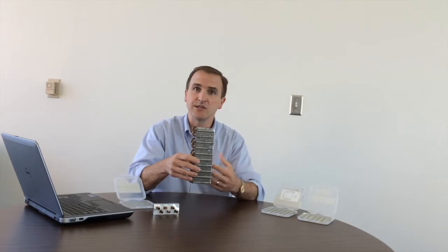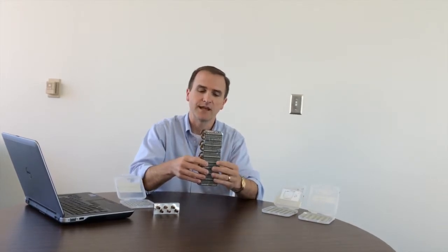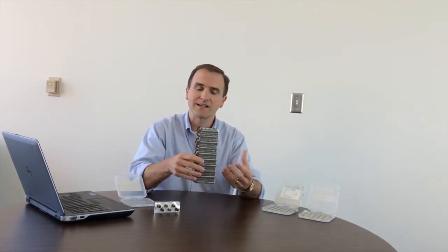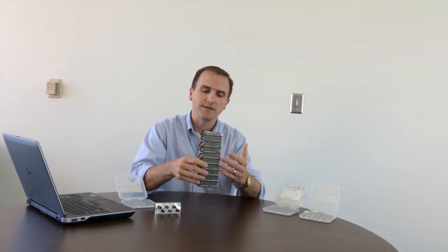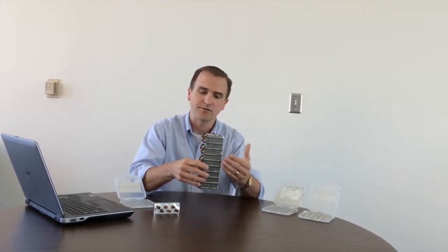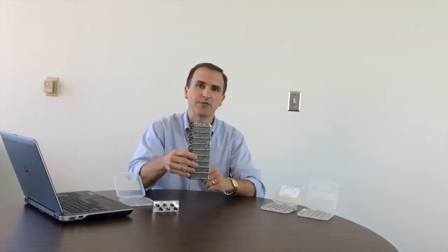It can decrease the heat transfer performance of the actual unit. That water is now occupying surface area that otherwise would be more readily available for heat exchange. The pressure drop across the heat exchanger generally goes up. Your fan has to work harder to move the same amount of air through the heat exchanger.